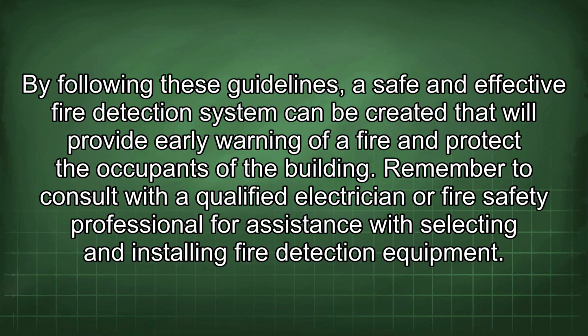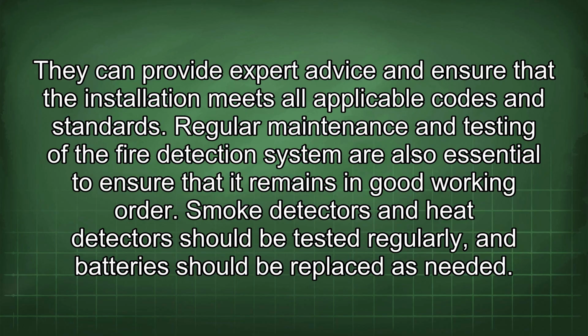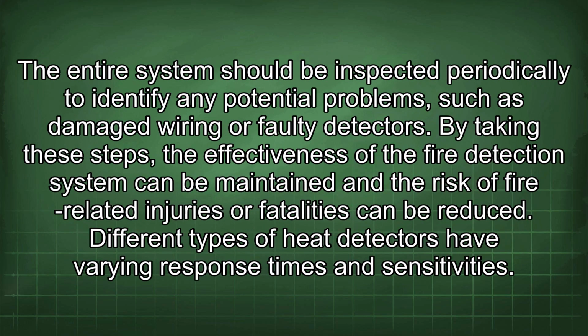Remember to consult with a qualified electrician or fire safety professional for assistance with selecting and installing fire detection equipment. They can provide expert advice and ensure that the installation meets all applicable codes and standards. Regular maintenance and testing of the fire detection system are also essential to ensure that it remains in good working order. Smoke detectors and heat detectors should be tested regularly, and batteries should be replaced as needed. The entire system should be inspected periodically to identify any potential problems, such as damaged wiring or faulty detectors. By taking these steps, the effectiveness of the fire detection system can be maintained and the risk of fire-related injuries or fatalities can be reduced.